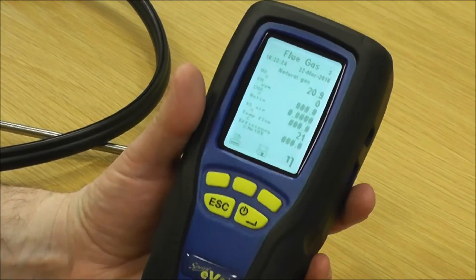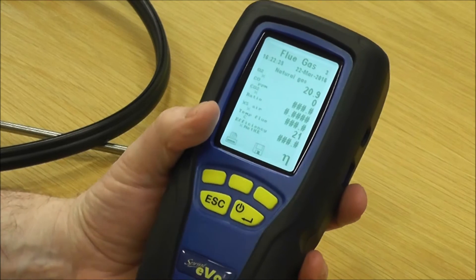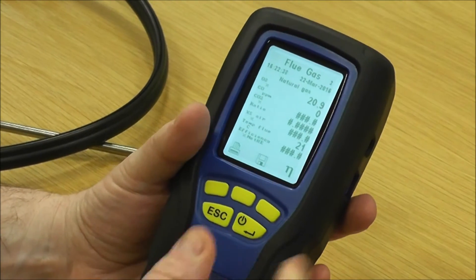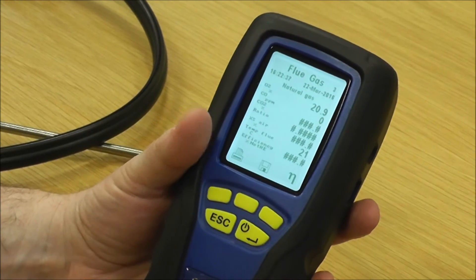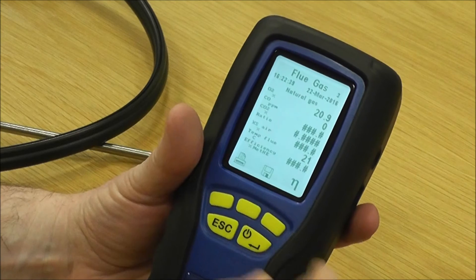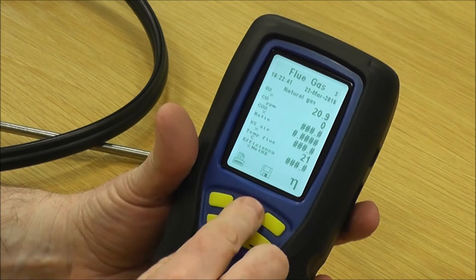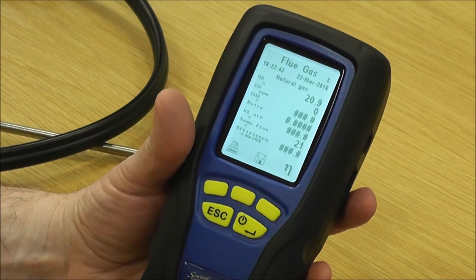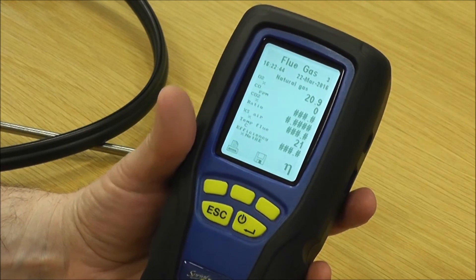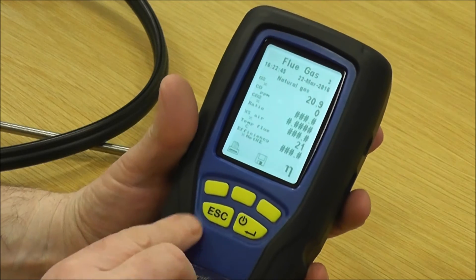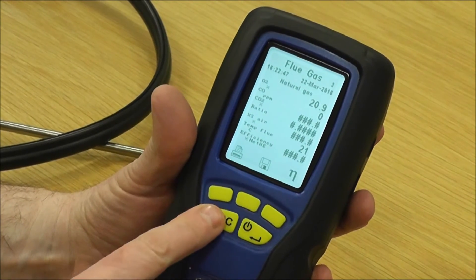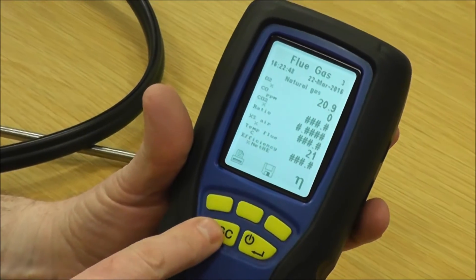That's how you set up your flue gas analysis. Simply put the probe in the flue — normally within about a minute you've got all your readings, they stabilize, you save them, and then you can print them.